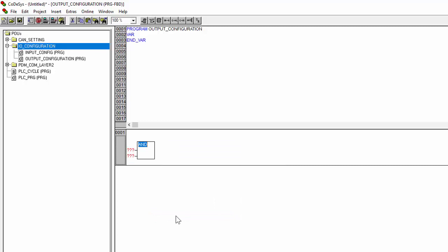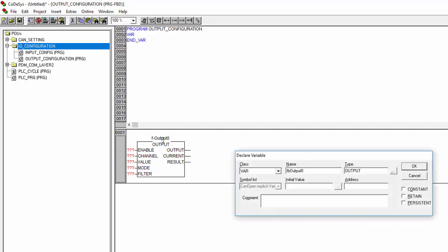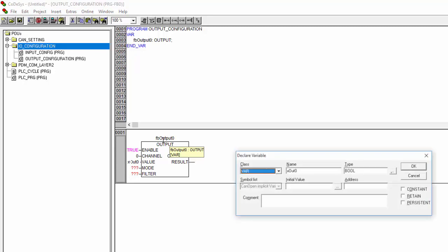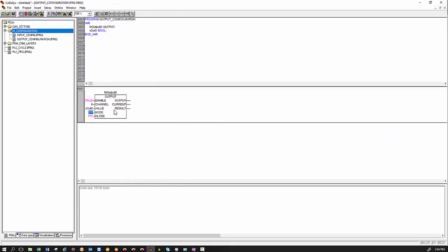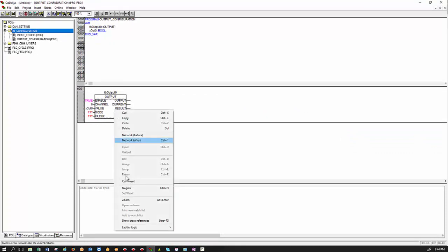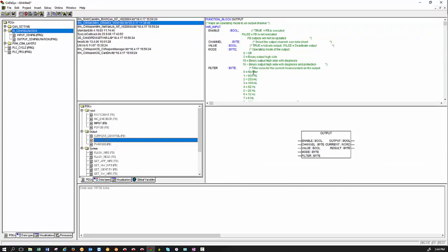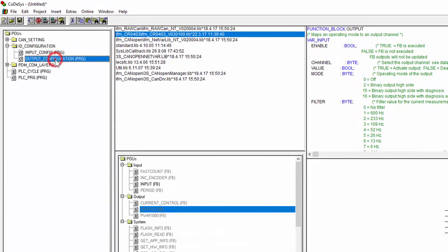And in order to configure an output as a digital output, you just use an output function block. We give it a name, zero, zero, so we give that true, channel is zero, value is, this would be the variable that will actually trigger the output. So this could be x_out_zero and you define that as a boolean value. And the mode, once again, you just right click on output, zoom and select output function block this time. And then in our case, we just select number two as we just want to be a binary output high side. We're going back to the program. So we make the mode two and the filter as four.